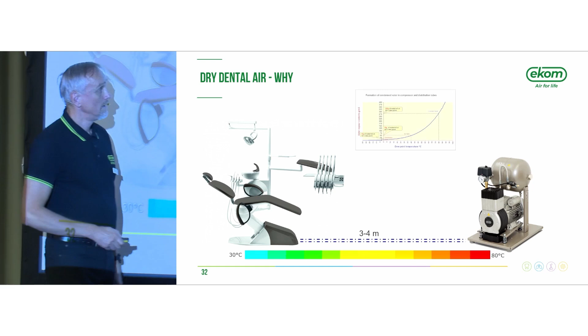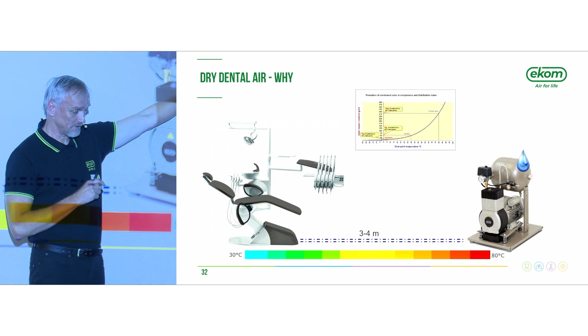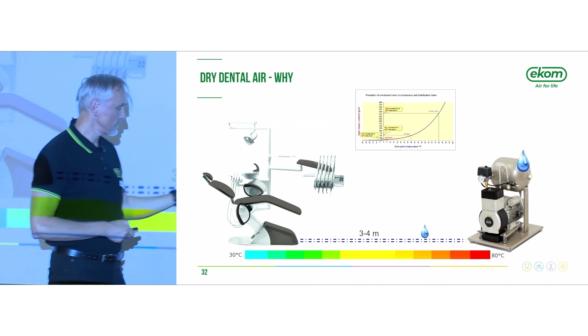Considering that physics, in the tank, which acts as a cooler, we get around 40 degrees Celsius, so going from 80 to 40. So much water will condense in the tank. Some water will condense in the hose, because the hose is again a cooler. Some water will condense in the dental unit. And of course, with the flow of air, you will push that water out of the system, so you get water in the instruments.